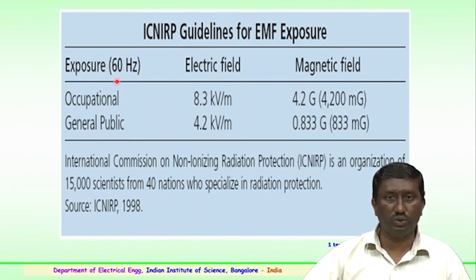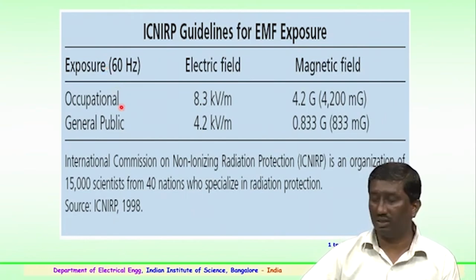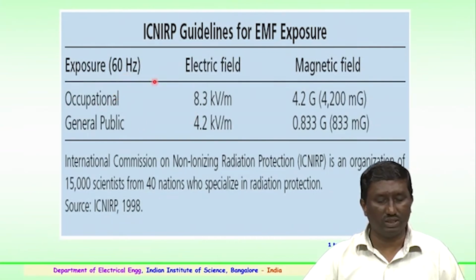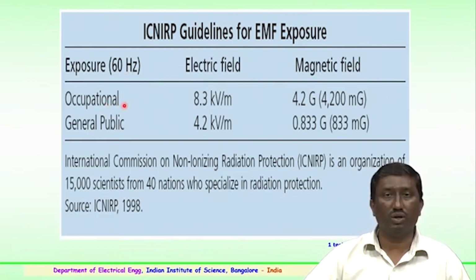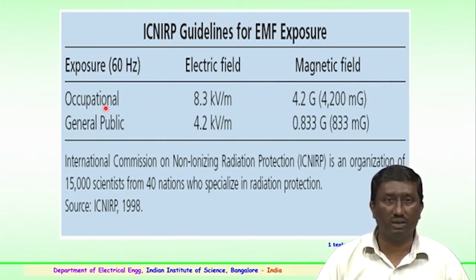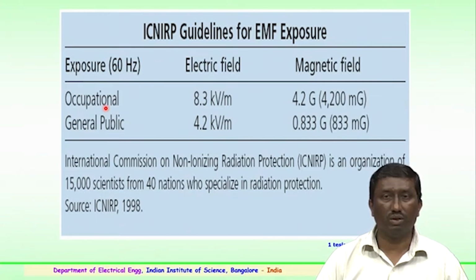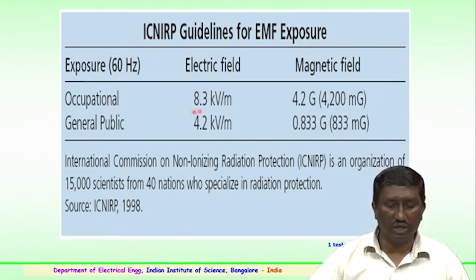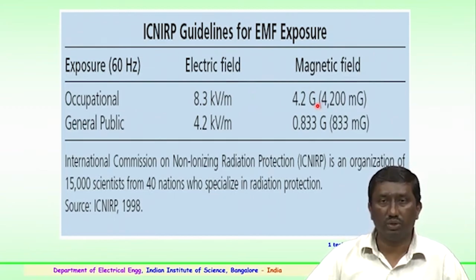You can see here the exposure for 60 hertz power frequency supply, 60 or 50 hertz. In our country it is 50 hertz, while some countries follow a 60 hertz supply. The guidelines for occupational exposure, that is, people working in the utilities, say in substations, or people exposed to transmission or substation electric and magnetic fields, say they should not be exposed to more than 8.3 kV per meter in the case of electric field, and in the case of magnetic field the maximum exposure should not be more than 4.2 gauss, or 4200 milligauss.